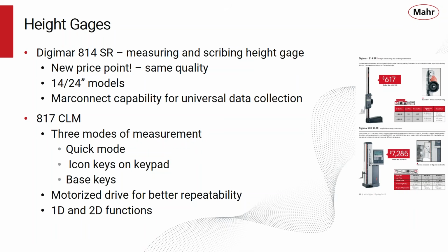And to make it even easier for the operator, it has 3 modes of measurement. We have some nice, simple to use icons on the keypad. You push the down measurement and it makes a downward measurement. We also have a quick mode, and basically what you do in the quick mode is just start dragging the head towards the surface you want to measure, release it, and then the head will continue to go down or go up, touch the part, and make the measurement. So you can make measurements without touching any keypads on the unit.